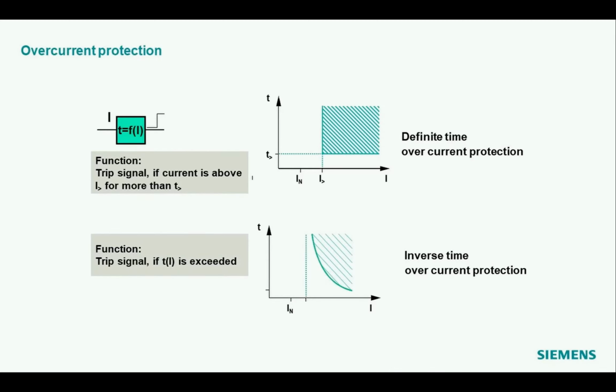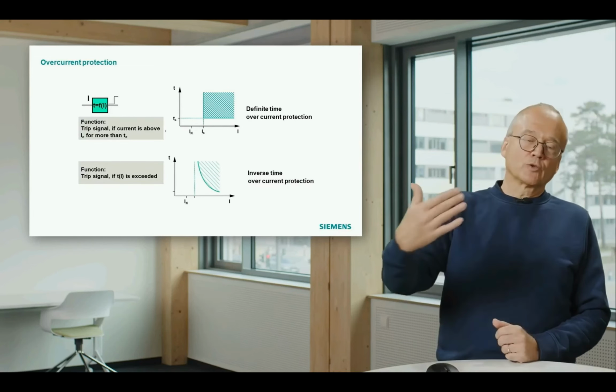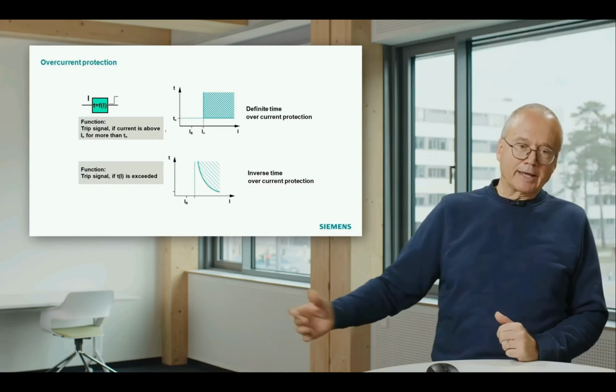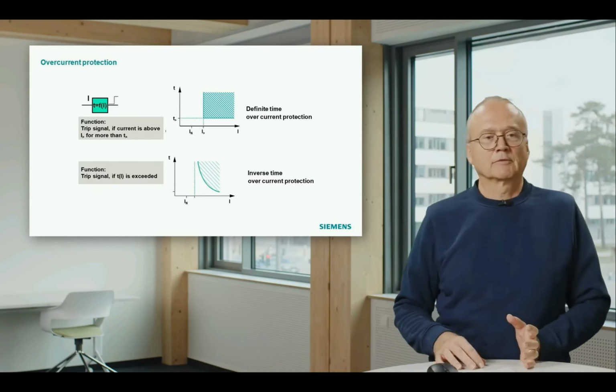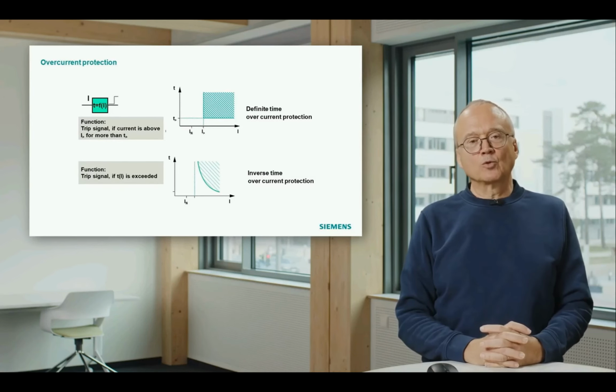Another alternative for this block is the so-called inverse time overcurrent protection. There you have, first of all, a similar situation. That means as long as you are in the load current area, you have no trip. Trip time is infinite. As soon as you are above a set value, it means, yes, I detect a short circuit, but then the trip time depends on the amount of current we detect. That means if we are slightly above our limit, we trip with a longer delay time. If we have very high current, we trip with a shorter delay time. That's a typical characteristic you may know from fuses.